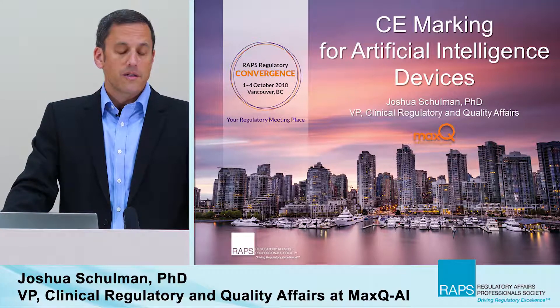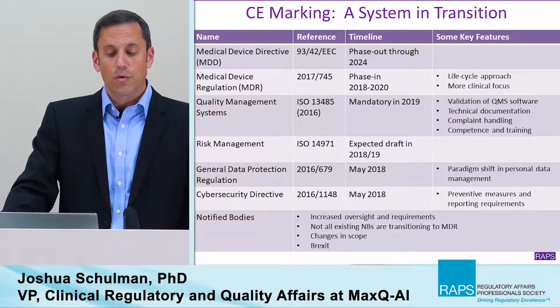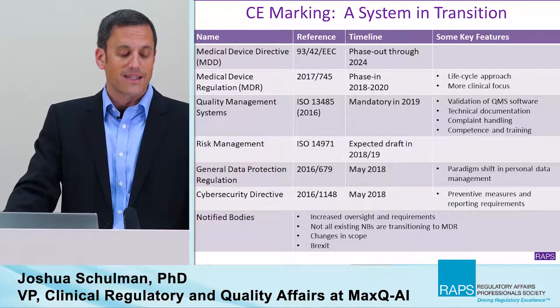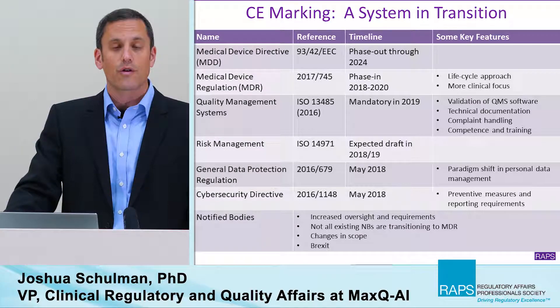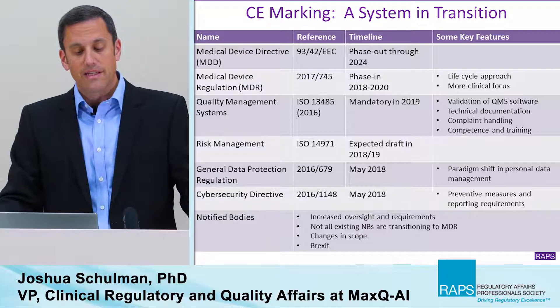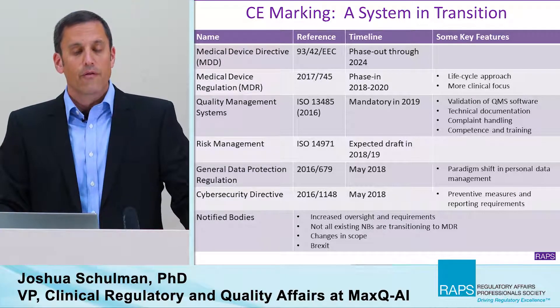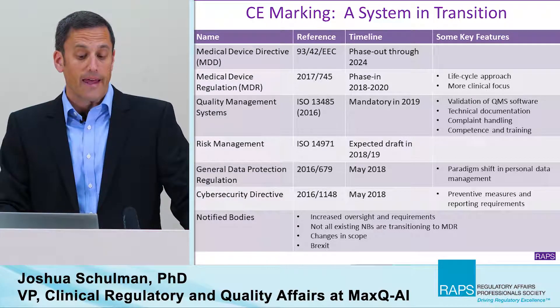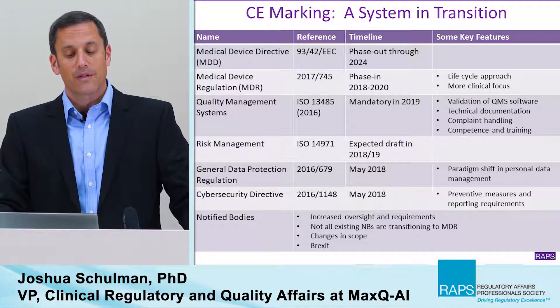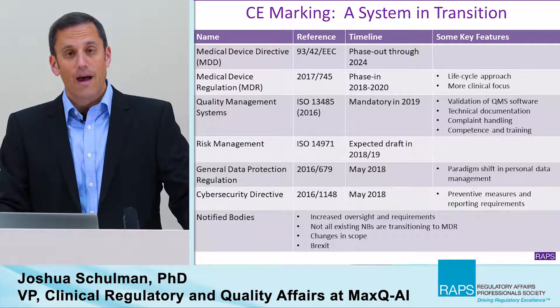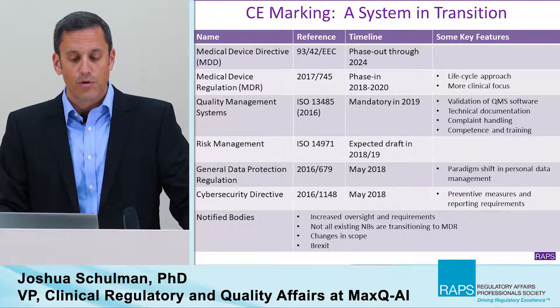To begin speaking about the CE system, it's worth thinking about the CE marking system in general. Currently, it's a system that's really in transition. I've listed some of the major documents and references that underlie this system, beginning with the Medical Device Directive. This is a directive that's been around for a number of years but is now in the process of being phased out. The phase out will take through 2024.